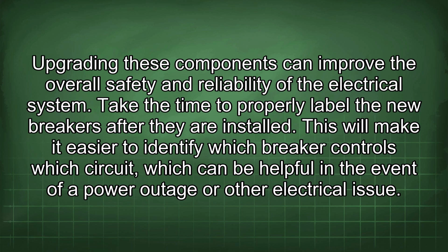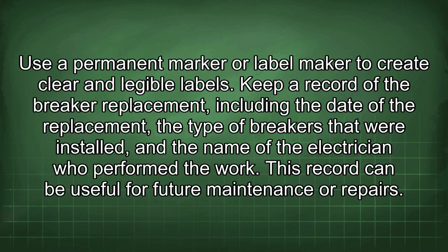Take the time to properly label the new breakers after they are installed. This will make it easier to identify which breaker controls which circuit, which can be helpful in the event of a power outage or other electrical issue. Use a permanent marker or label maker to create clear and legible labels. Keep a record of the breaker replacement, including the date of the replacement, the type of breakers that were installed, and the name of the electrician who performed the work.